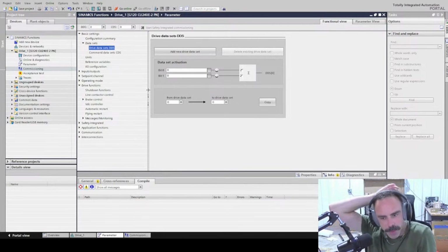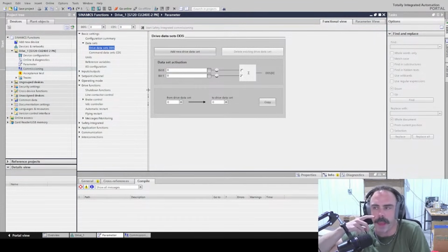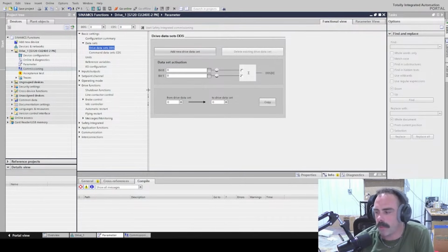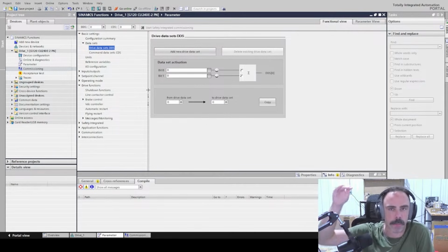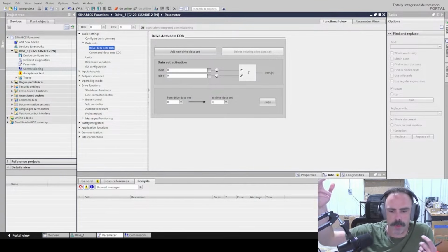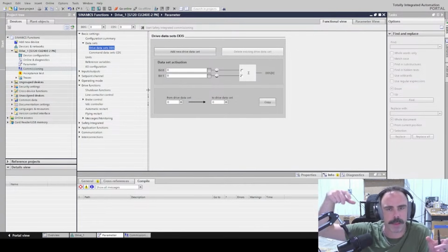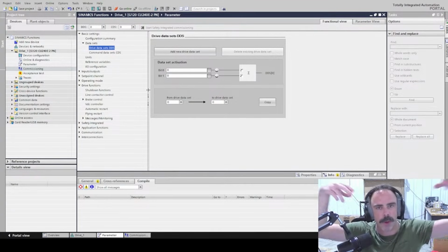Well, those need to be metered and need to have drives. And it's like, okay, you have to have 13 drives in order to run these, right? Well, no, you don't. Because technically, at most, you're going to be running 2 of those feeder screws at the same time, because every ingredient can only be weighed out one at a time. And then there's only a couple of bins that have the same ingredient in them.